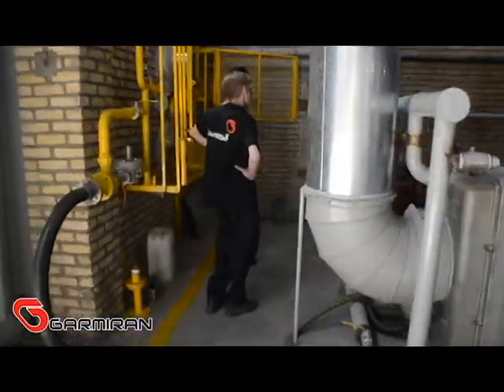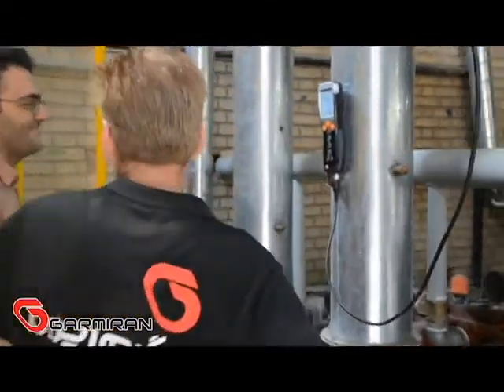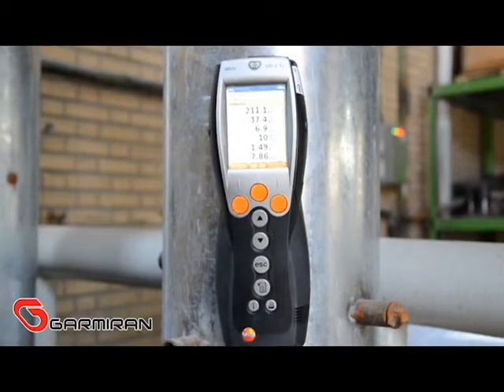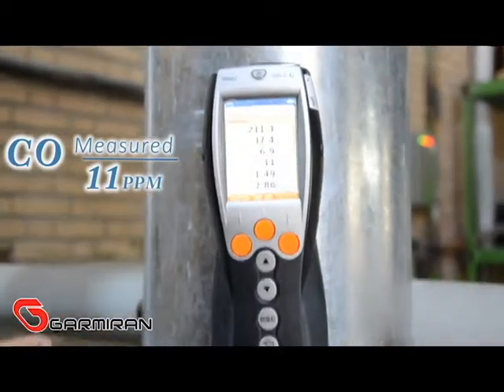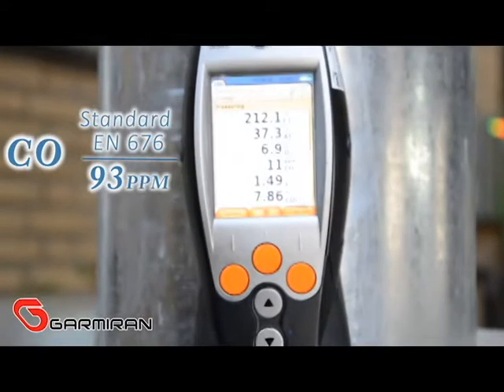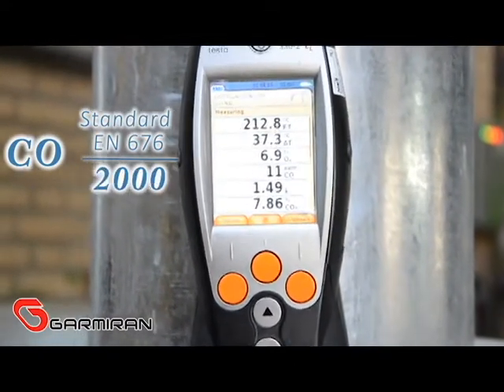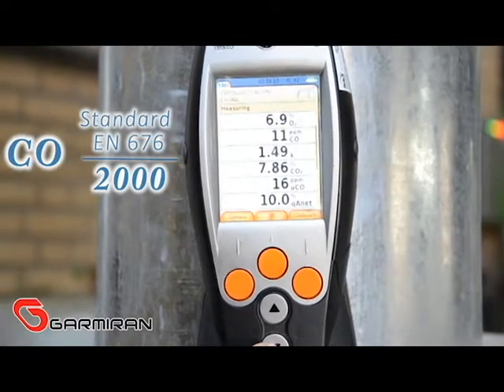We measure the NOx and emissions of the flow by Testo analyzer. The amount of CO of this burner has been measured at 11 ppm; however, EN 676 standard allows up to 93 ppm for reference test gas and 2000 ppm for natural gas.